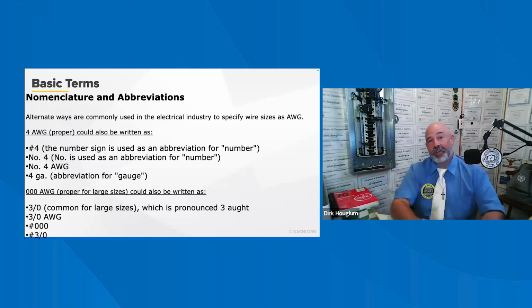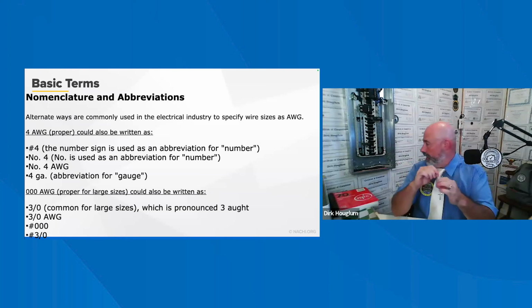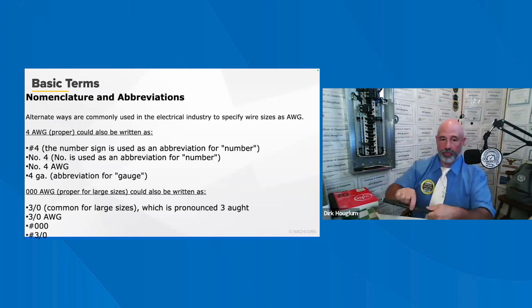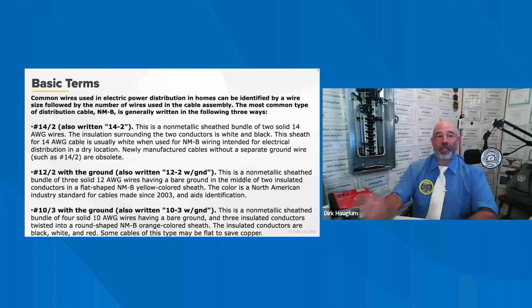I totally get it. The basic terminologies that we use is, like I said before, the AWG. So a number 4 AWG would be abbreviated as just the number 4, or 4 AWG, or 4GA. Once you get larger, the number goes down. So 4 is not as big as 3, and 3 is not as big as 2, and so on and so forth. Okay. But 3 would actually be pronounced 3-aught. So it does get a little confusing. But if you look on the wire itself, if you're looking at something like this, it would say 3. This isn't a 3, but it would say 3, or it would have 000 printed on it. So that's how you can kind of tell the difference. And you'll get it after a while.